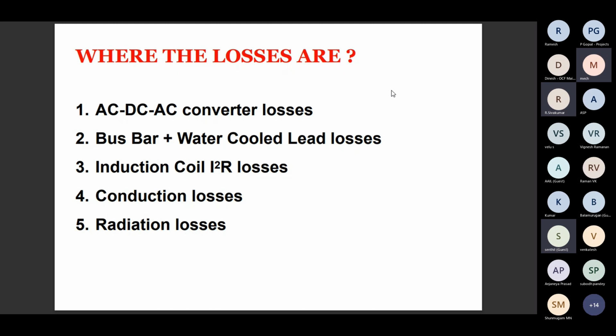Nowadays, dual secondary transformers are available for the small industry furnaces, so that one secondary is used for the induction side, the furnace side, and another secondary is used for the auxiliary loads. So this particular AC voltage is fed into the furnace main panel. It converts from AC to DC. Again, this DC is smoothened, and again converted into AC. The mid-range frequency furnaces operate at up to 1000 hertz. But on the primary side, we are using only 50 hertz, whereas the coil side uses up to 1000 hertz. That's why it's called mid-range frequency.